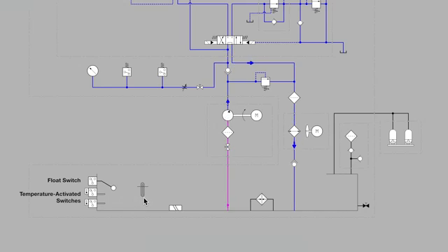Another mercury bulb symbol shown here is for a sight glass that lets us see the level of the fluid in the tank, but also the current temperature. The symbol shown here at the bottom, which came from this drawing that is 40 years old, was a bit of an error. The rectangle with a single diagonal slash through it is an electrical solenoid. Two diagonal slashes would indicate a solenoid with two windings.